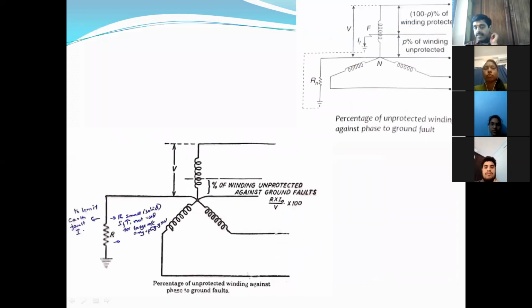Let us see this. This is an important picture for solving problems also. Here you see there is a fault in one of the windings. This is the phase voltage V, and this is the percentage of the winding unprotected. You can get problems on this percentage of the winding unprotected. The percentage of the winding unprotected against ground faults can be obtained as R into I naught by V into 100, where V is the phase voltage.